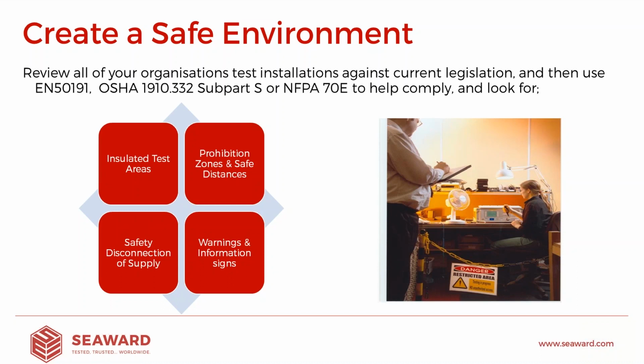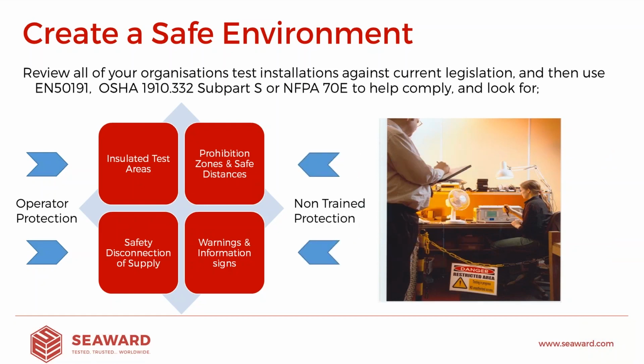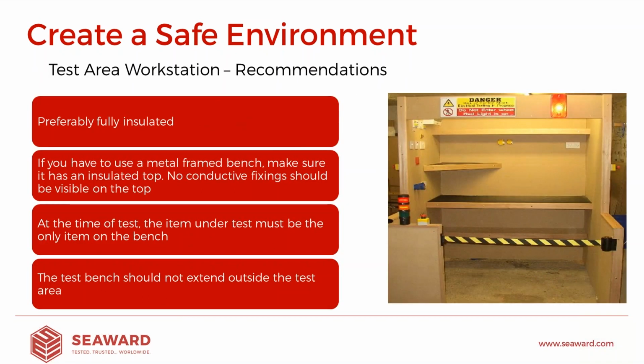Now, these things can be broken down into two clear parts, really. The first ones, insulated test areas and safe disconnection of supply, are all about protecting the operator, the person in the test area actually performing the tests. The second few are all about keeping non-trained personnel safe. So this is keeping people well away from the area, allowing them to see quite clearly what the area's use is, and therefore that they can understand that it's not an area that they should be in. So if we start to break these things down into single elements, we can start to talk about the pieces of the jigsaw puzzle that will ultimately come together to create a safe working environment.